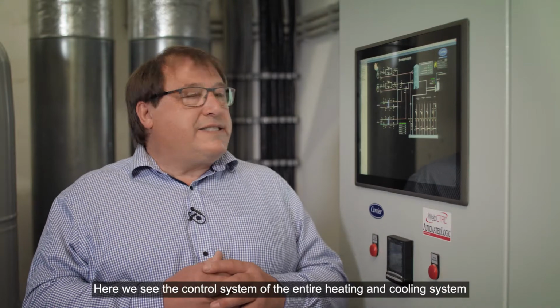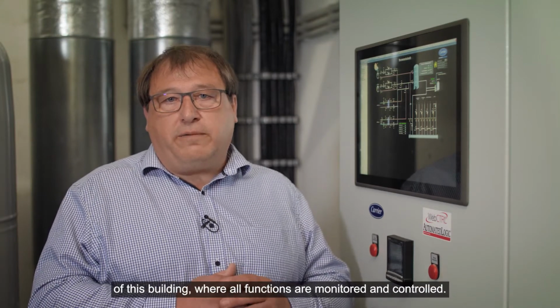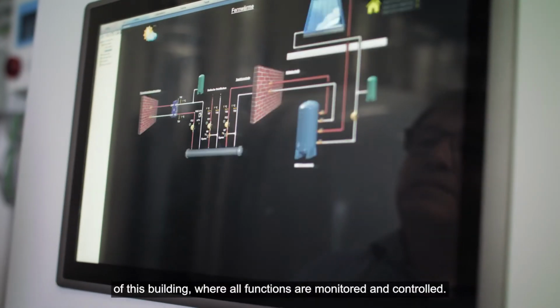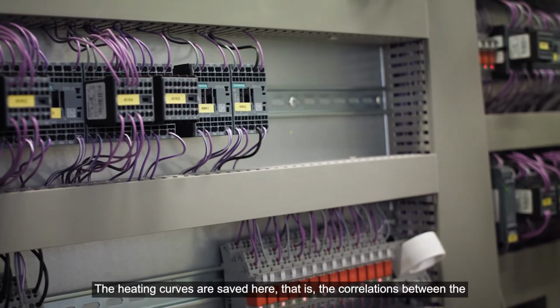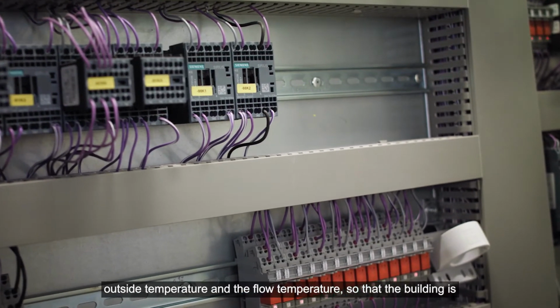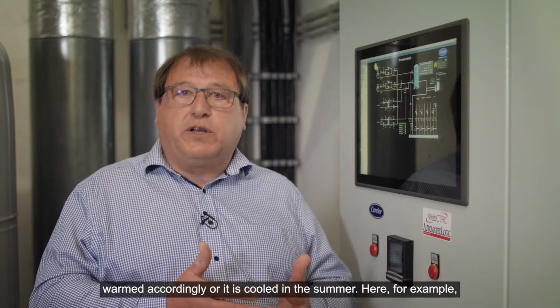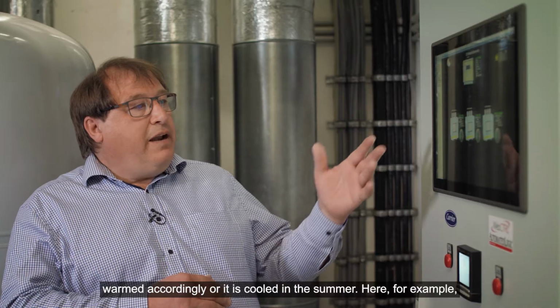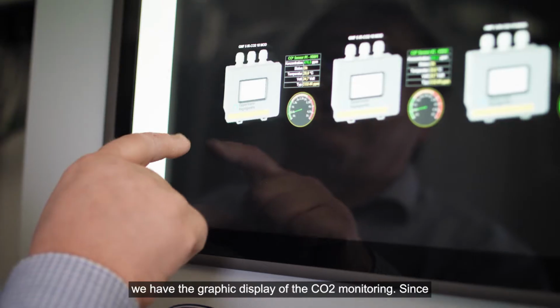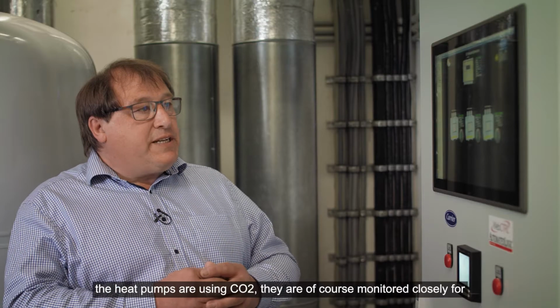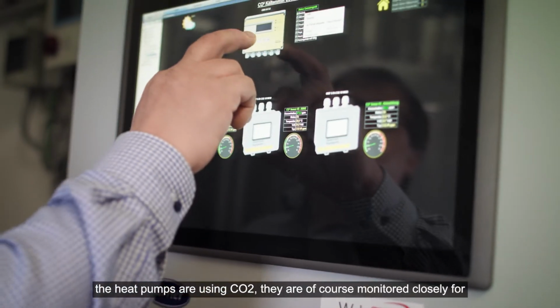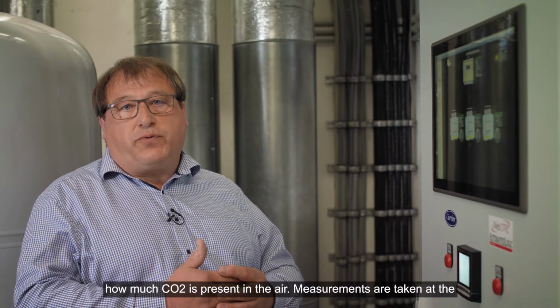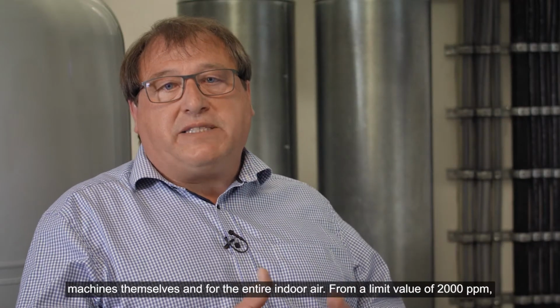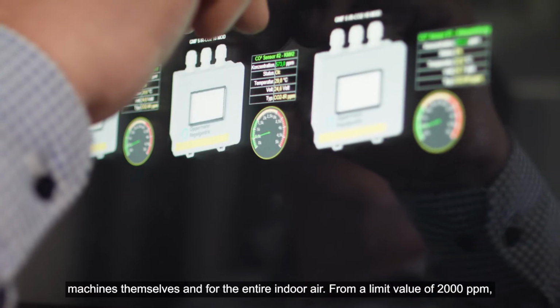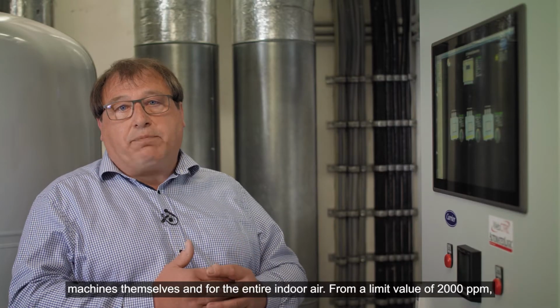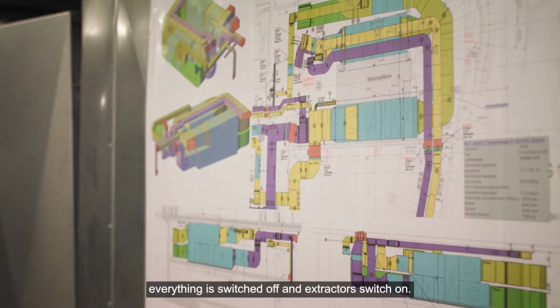Here we see the control system of the entire heating and cooling system of this building, where all functions are monitored and controlled. The heating curves are saved here, that is, the correlations between the outside temperature and the flow temperature, so that the building is warmed accordingly or it is cooled in the summer. Here, for example, we have the graphic display of the CO2 monitoring. Since the heat pumps are using CO2, they are of course monitored closely for how much CO2 is present in the air. Measurements are taken at the machines themselves and for the entire indoor air. From a limit value of 2000 ppm, everything is switched off and extractors switch on.